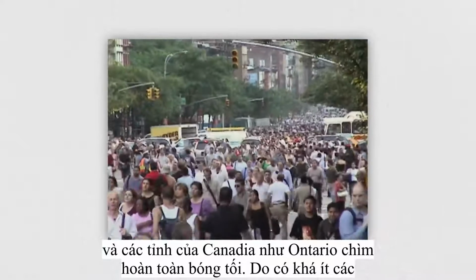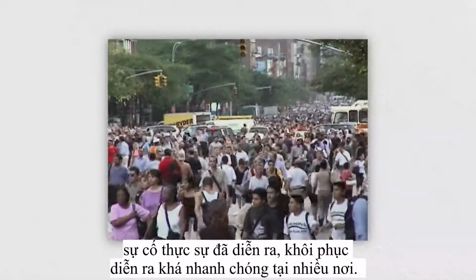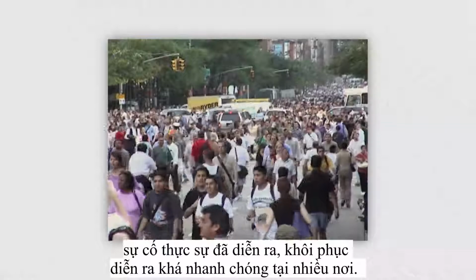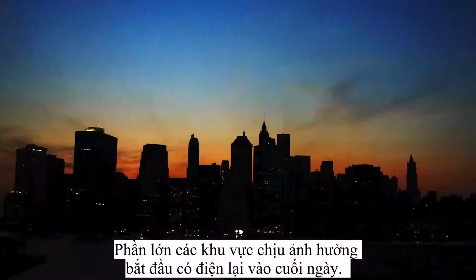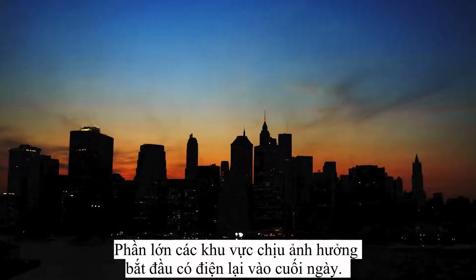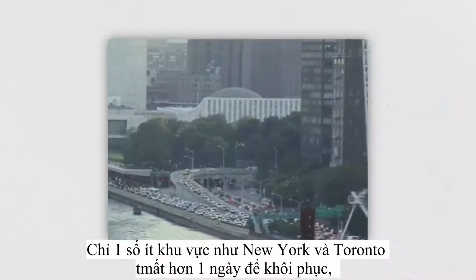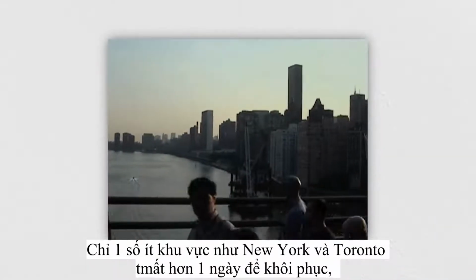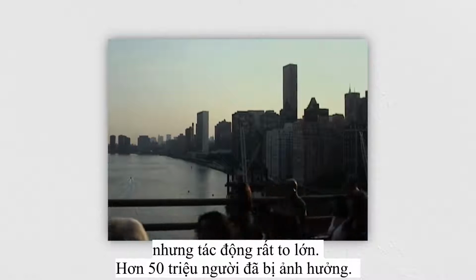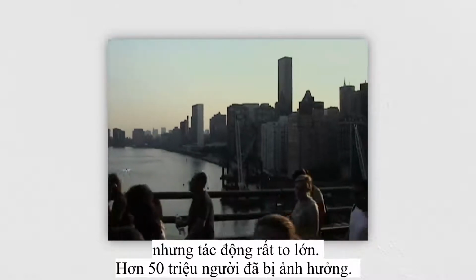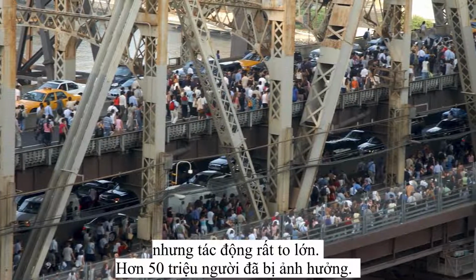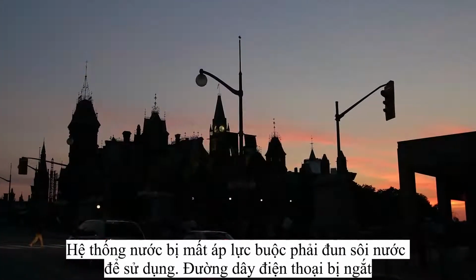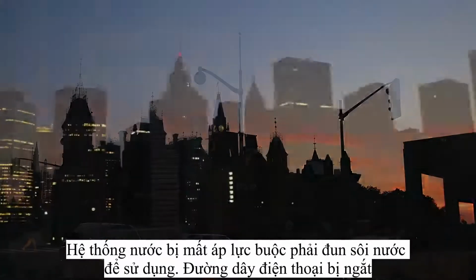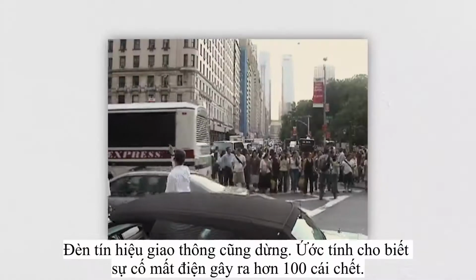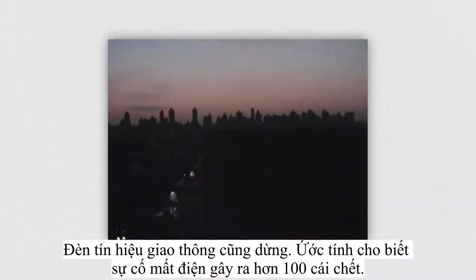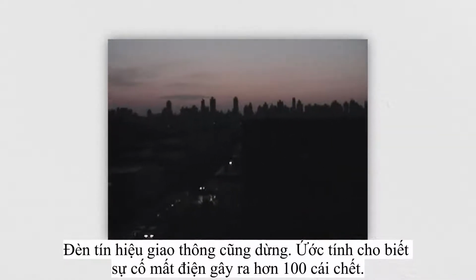Since there were very few actual faults during the cascade, re-energizing happened relatively quickly in most places. Large portions of the affected area had power back on before the end of the day. Only a few places in New York and Toronto took more than a day to have power restored, but still, the impacts were tremendous. More than 50 million people were affected. Water systems lost pressure, forcing boil water notices, cell service was interrupted, all the traffic lights were down. It's estimated that the blackout contributed to nearly 100 deaths.